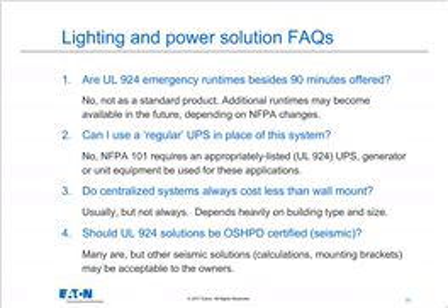and requires, for example, that the UPS not only survive earthquake-related forces, but continue to operate at the end of the event. So many 924 solutions are OSHPD certified, but other ones use calculations for seismic compliance, special mounting brackets, etc., and that may be acceptable to the owners and the authority having jurisdiction. So OSHPD is not required, but it is a desirable feature to have in an emergency lighting UPS, just like a data center UPS.